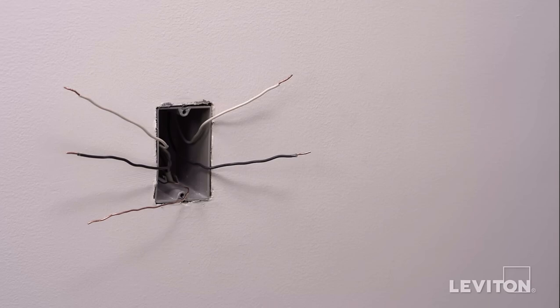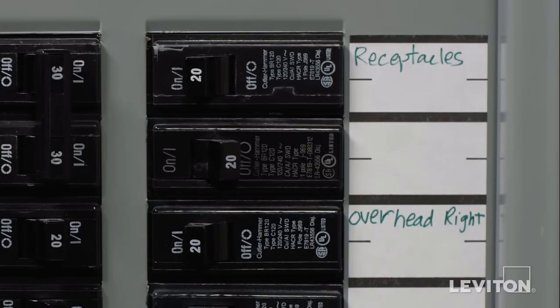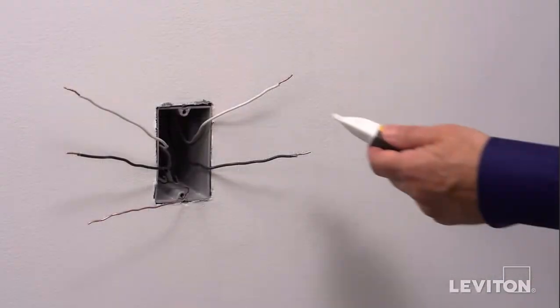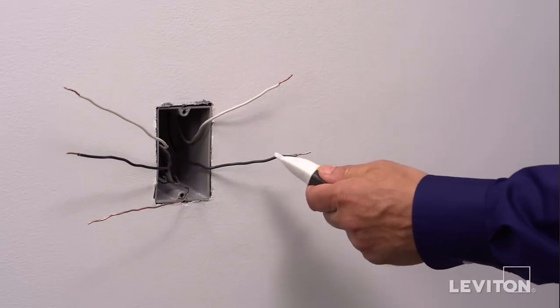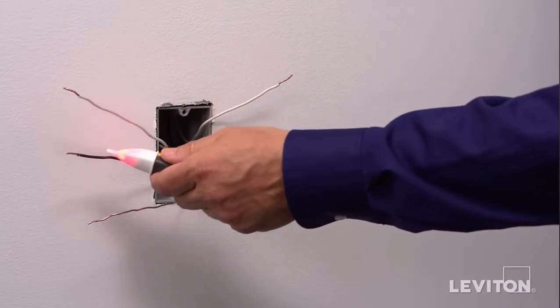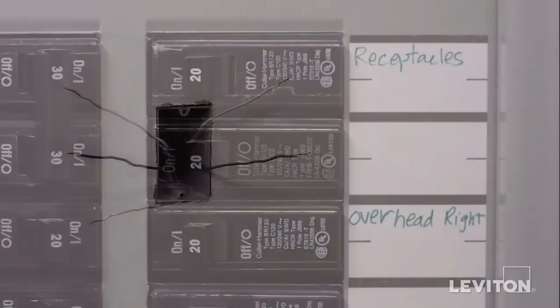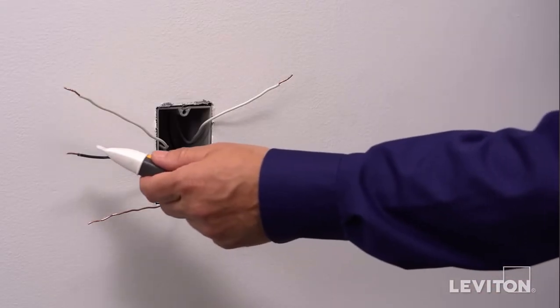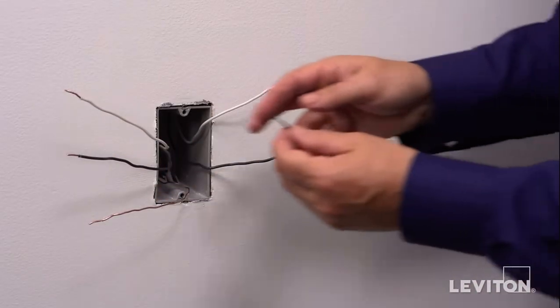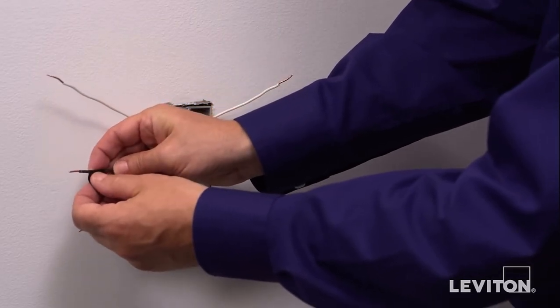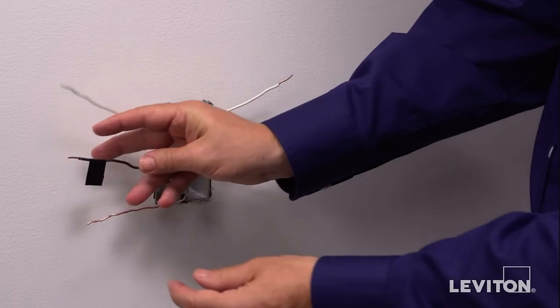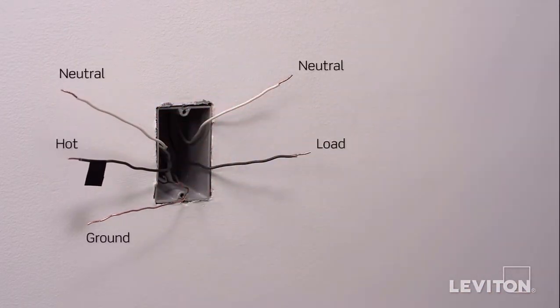Now, we need to identify the hot wire. To do this, turn the circuit breaker back on. Carefully use the voltage tester to test each wire. The hot wire will be indicated by the tester. Once identified, turn off the circuit breaker to shut power and test to ensure that the power is off. Use a small piece of electrical tape to label the hot wire. Note that in this example, there is a black hot line wire, a black load wire, 2 white neutral wires, and a bare copper wire, which is the ground.